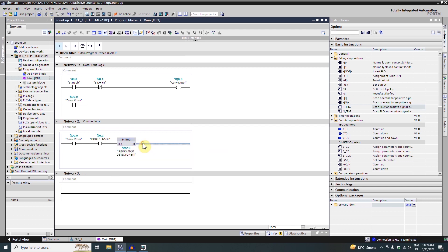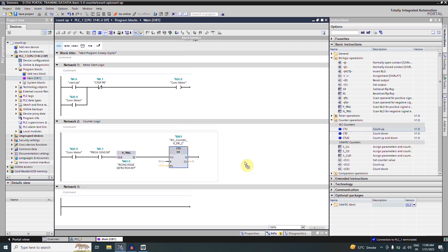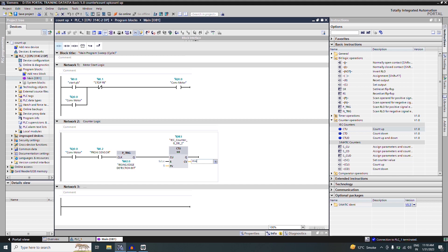Next we will insert a counter — we will be using the count-up instruction today. We drag and drop the count-up instruction, and for the preset value PV we will enter five, as we want to count five boxes. CV means the current value, and we will be storing the current value of this counter into memory word MW10.